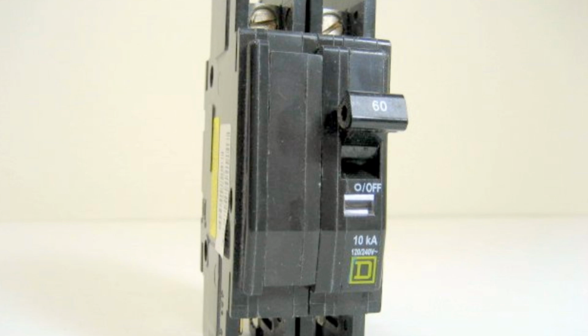But 15, 20 amps is typical. You also have a double pole breaker, which is more common for where your range or refrigerator is plugged in, because they can handle more amperage, up to 15 to 30. Those are the two most common types of breakers you're going to find in a house.